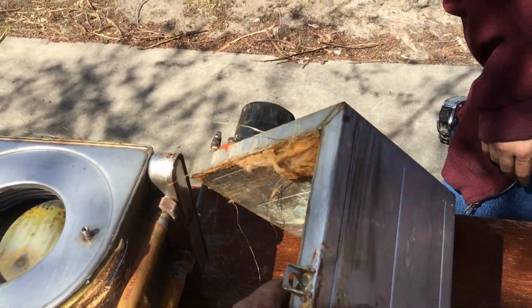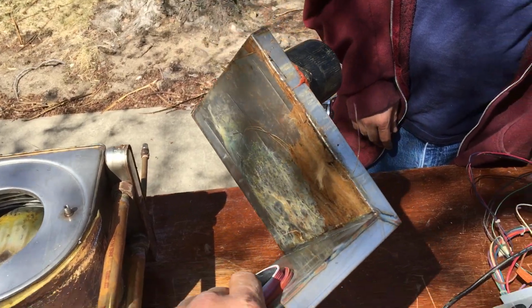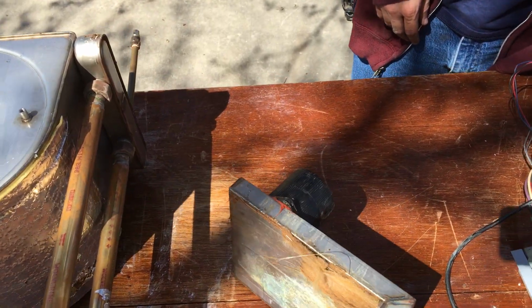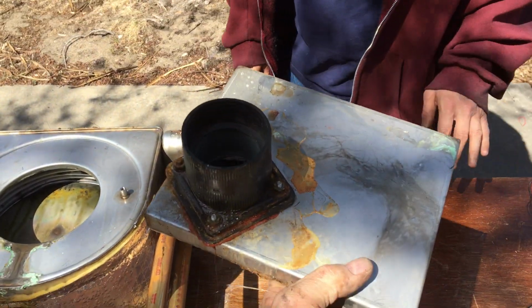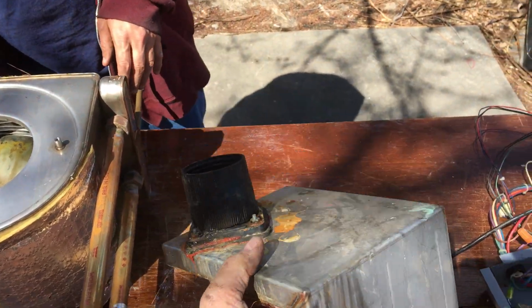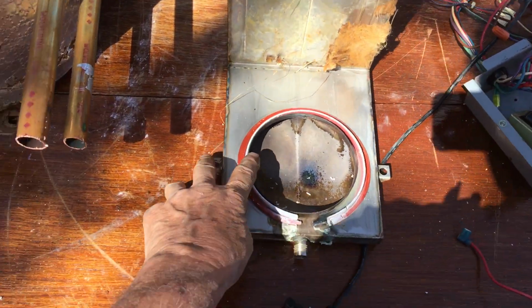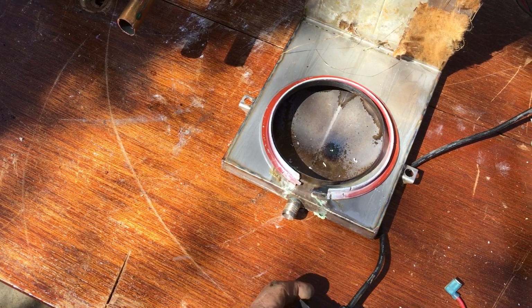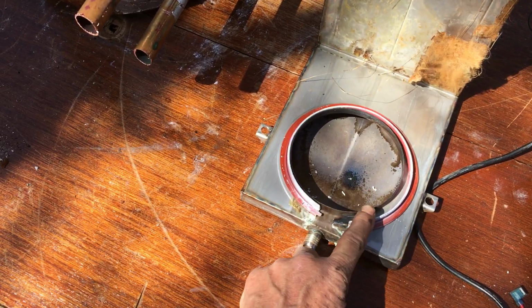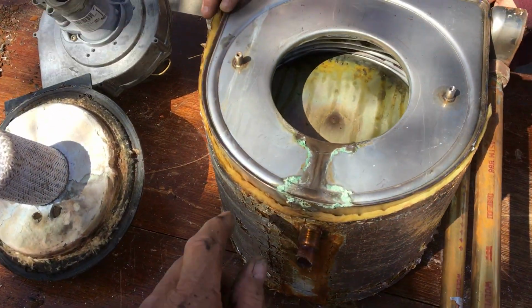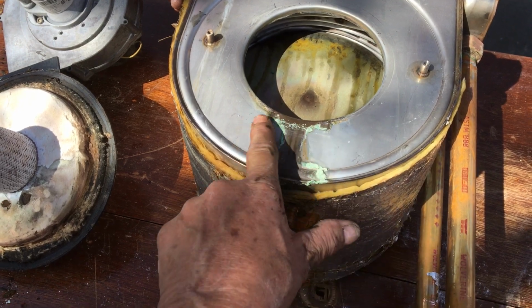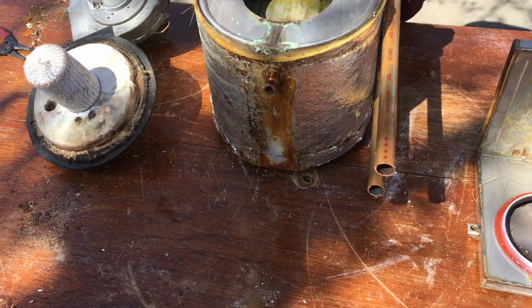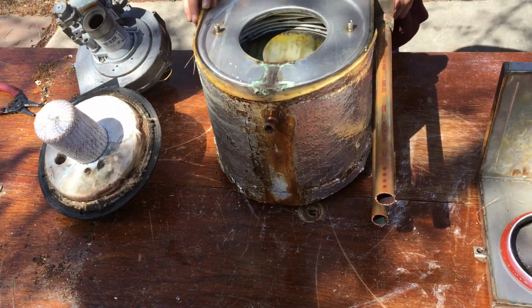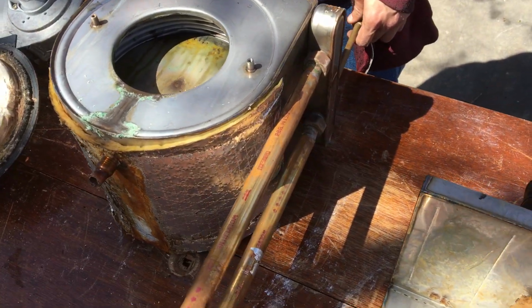This is the smoke hood that I mentioned earlier. That was the weak point where the PVC attached to it. You can see the gasket has broken here and was leaking big time. That's where much of the corrosion you saw on the case earlier came from.